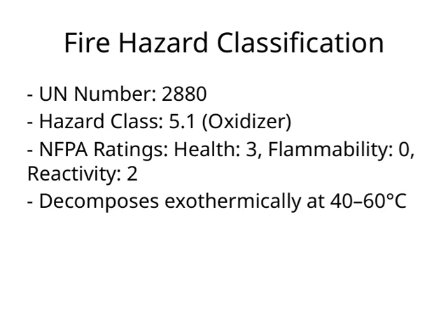An important point to note is that this substance decomposes exothermically. That is, it releases heat when heated to temperatures between 40 and 60 degrees Celsius. This means that if it's exposed to heat within this range, it could start breaking down and generating heat, potentially leading to dangerous situations. Understanding these points helps us grasp the fire hazard classification of this material.